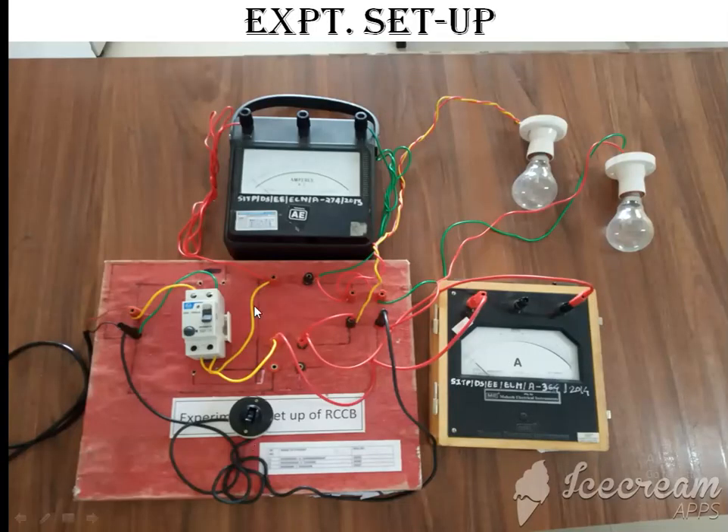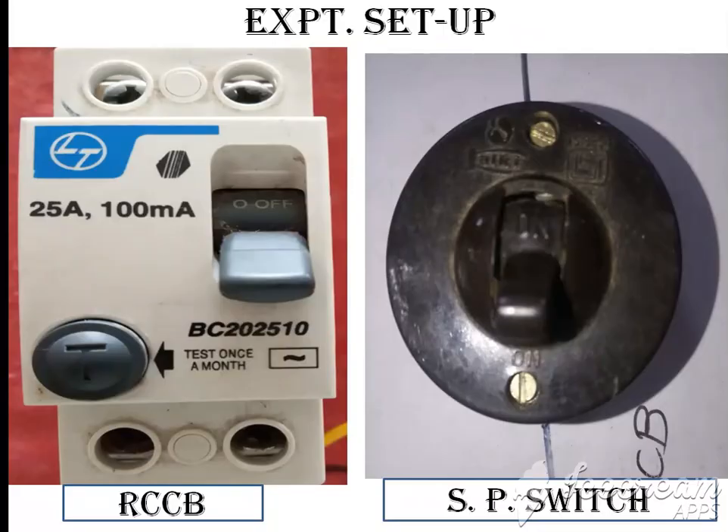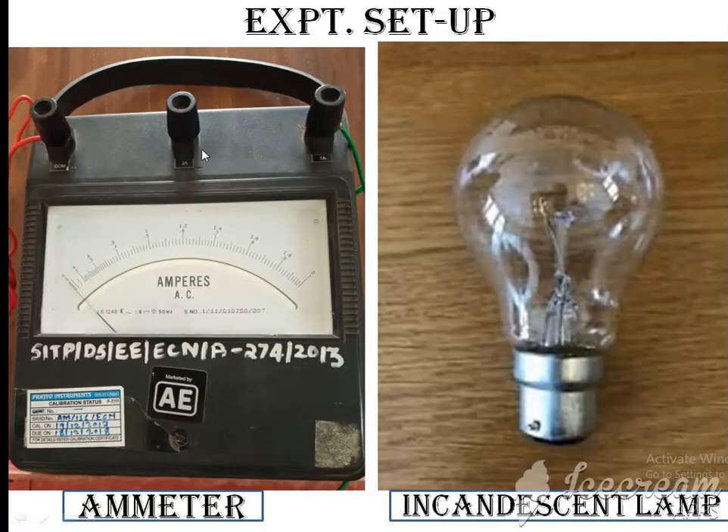This is the actual experimental setup of our circuit. This is the RCCB — rated 25A, 100mA — where 25A is the current rating capacity and 100mA is the sensitivity, meaning earth leakage current capacity. Make is L&T. This is the SP switch used instead of a knife switch to bypass the RCCB. Next, we have the ammeter: 0 to 1 to 2 ampere capacity, make Automatic Electrical. Last is the incandescent lamp, rated 100W, 240V. These are the resources required for our practical.